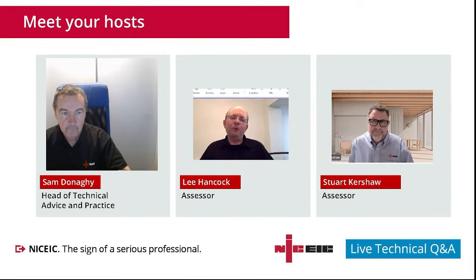I think the other thing to mention as well, Sam, when we talk about these boards, there's still plenty of them out there in service. When these things were put in back in the 60s and the 70s, possibly the early 80s, installations weren't as complex as they are now. A lot of the appliances either didn't exist or they were relatively low loading. For instance, a 7.5 kilowatt shower nowadays, the norm seems to be 9.5, 10.8. Will the main switch of these boards handle these additional loads? And there is another consideration for possibly updating the consumer unit.